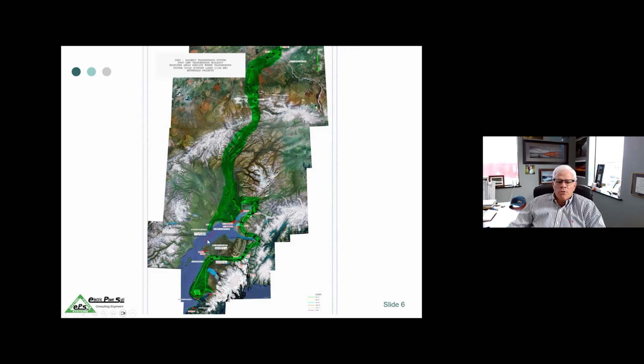This is a new HVDC cable link from the Homer system across to the Chugach system at Beluga, the old power plant. It's DC to prevent stability problems between the Kenai and Anchorage, and it will increase the export capability between the Kenai and Anchorage to somewhere over 250 megawatts.